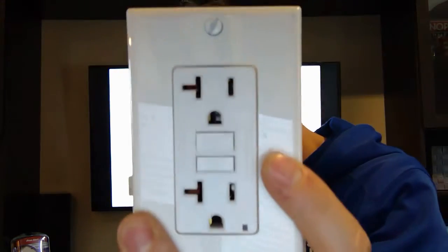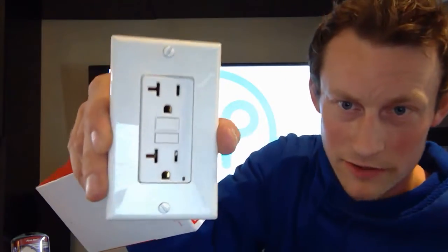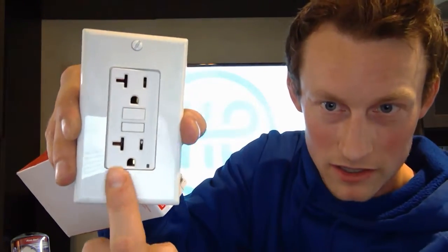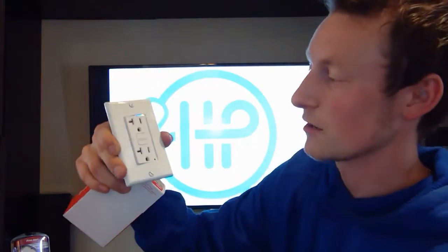Here we have 2. We have a 20 amp. This one's a little different. We've got a 20 amp GFCI receptacle. This one here is 20 amp, 120 volt rated. You can tell it's 20 amp right off the bat if you're a trained electrician by that T slot. You can see the hot slot is a T. Sorry, the neutral slot is a T. So your identified slot comes in the shape of a T.